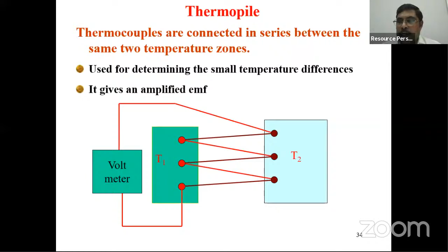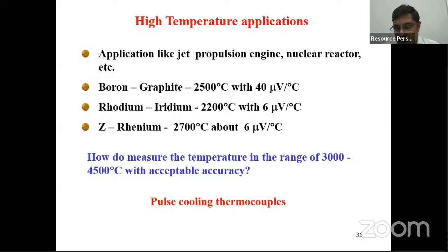Now if you want to measure high temperature, we have already seen that R, S and B type thermocouples can be used up to about 1700 degrees Celsius. If the temperature is above 1700, say up to about 2000 or 2500, which is sometimes required in a furnace or a melting system, here we can use boron and graphite thermocouples, but these are very expensive. Rhodium and iridium type thermocouples are also very expensive. But if you want a better or cheaper option, there is the pulse cooling thermocouple. Here, using a K or R type thermocouple, you can measure temperatures in the order of 2000 to 3000 degrees Celsius.